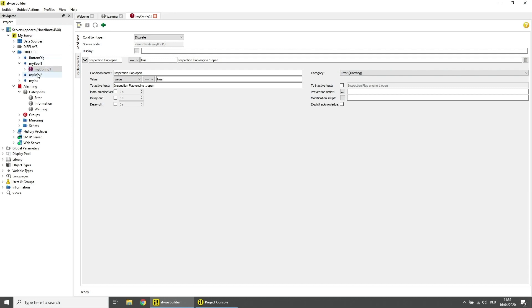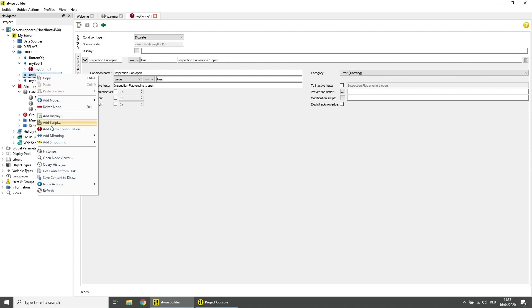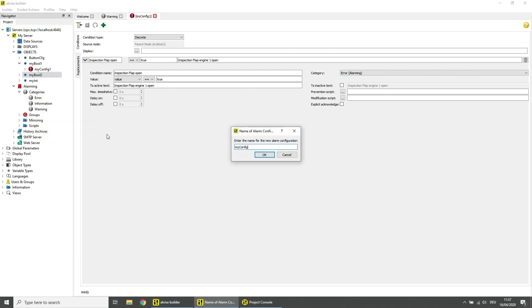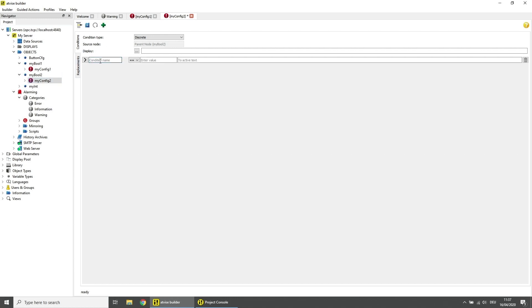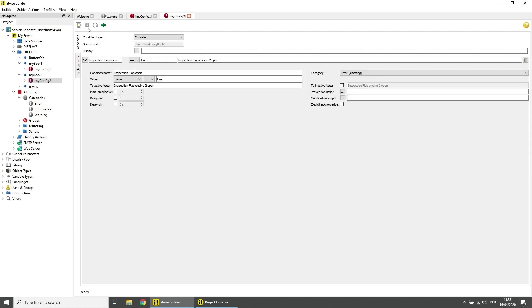Repeat adding an alarm configuration for the second boolean data variable. When adding the alarm condition, activate Delay On by checking the checkbox and setting the value to 5 seconds. Save the configuration.